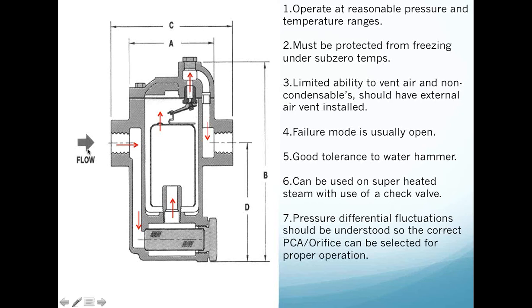And I need you to know this, that differential pressure is very, very important. I have a small story to share. A company recently mothballed a coal-fired power plant and put in a gas-fired power plant for a college. When they selected the new power plant, they changed the pressure of the actual power generation to the campus. When they did that, they did not necessarily stop and consider whether or not the traps actually had the correct size orifices based on the differential to process the condensate load that they could see.